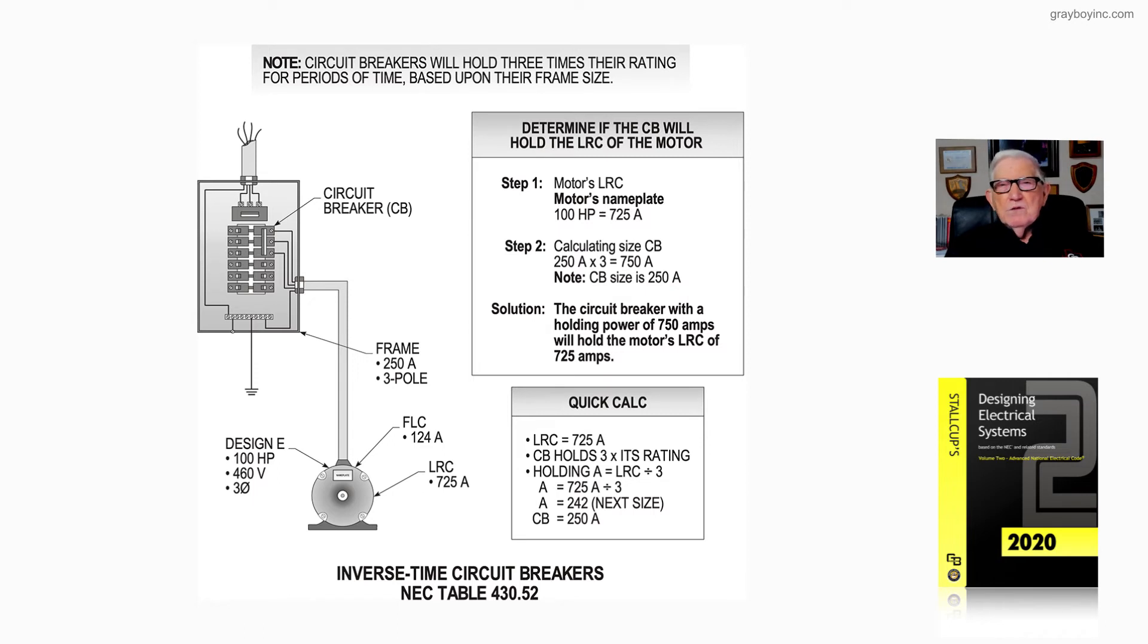You could just round that up to 250. Or say you come up with 260, then you could round down to 250 or round up to the next size in accordance with 430.52(C)(1). Remember round down size.